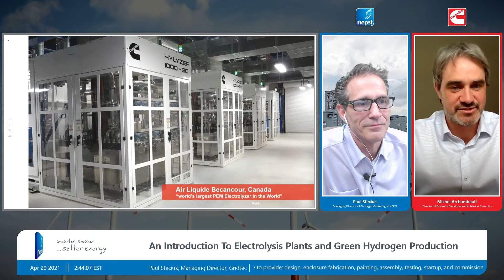If you look at harmonics and so on, you really do need to have a coordination study, because every site is different, in terms of whether you need filters or not. In some cases a plant like this may have synchronous condensers, which affect the power factor in some way. In other cases you're just connected to a renewable energy plant. So really, every site is specific and needs its own coordination study.